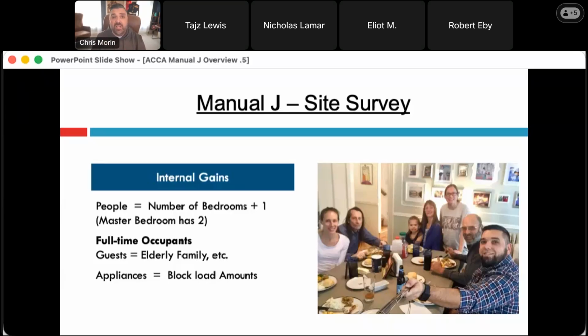Keep in mind the people should go into the rooms that they're going to be in during peak demand. So typically, like my daughter's a teenager now, so she's probably the exception. She's in her bedroom at 4 or 5 p.m. in the afternoon, but most people are not in their bedrooms. They're in a living room, maybe in a kitchen, in a home office. That's where you're going to put them because those gains could impact the airflow and the duct sizing going to those spaces or the distribution with ductless systems.